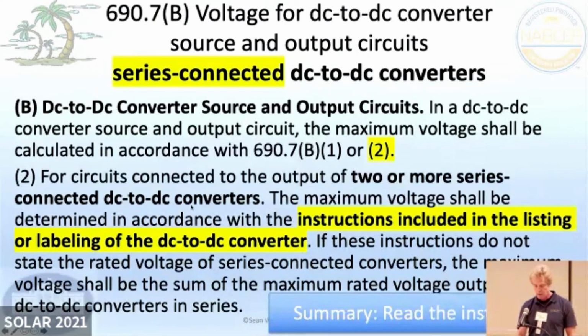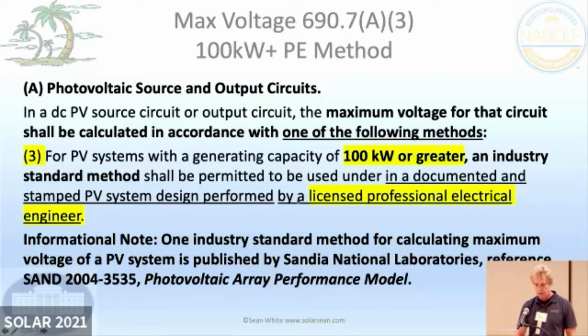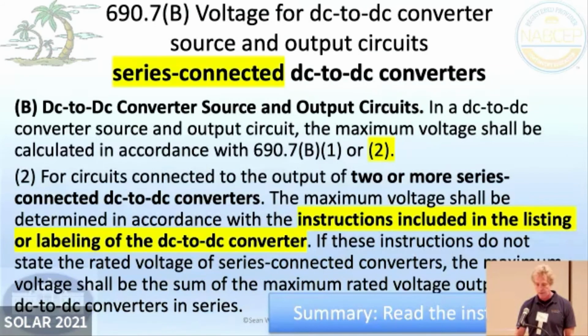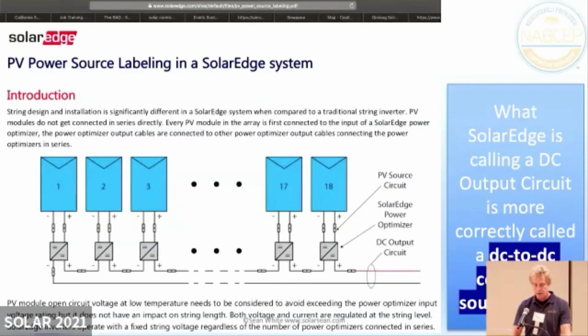And they tell you to maybe use an electrical engineer, because sunlight hits the PV module and the sun heats it up. And so that's kind of what they're looking at. And you can even put more in series under engineering supervision. Okay, and then for your DC to DC converters, for the voltage there you figure out how many you can put in series. I mean, you just read the instructions. It's electronic equipment. It'll tell you in the instructions what it'll do. Here's a DC to DC converter, the most popular type of system that you'll see on a building these days in the United States because of rapid shutdown requirements.